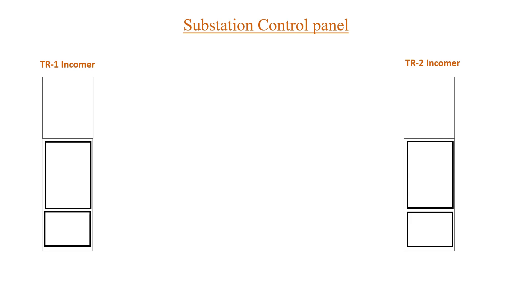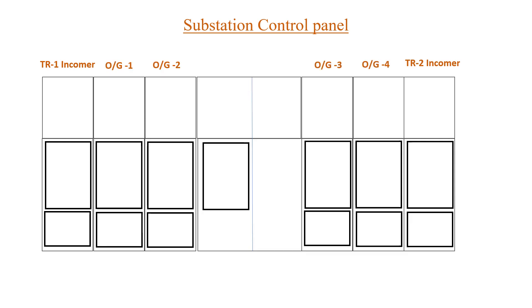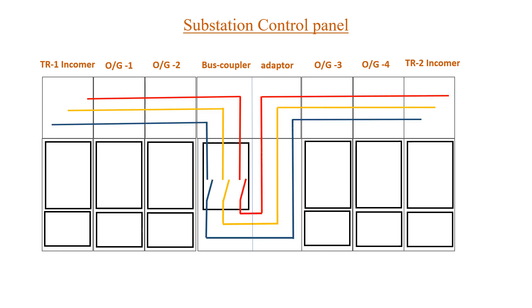This is the 11 kV panel board. We have already discussed about this kind of panel board in our PT selection video. There are incomers on both the ends of the panel and then there are different outgoing feeders. They are connected with the bus coupler and adapter system as shown over here. The busbar arrangement is something like this and we have PTs on both the incomers.